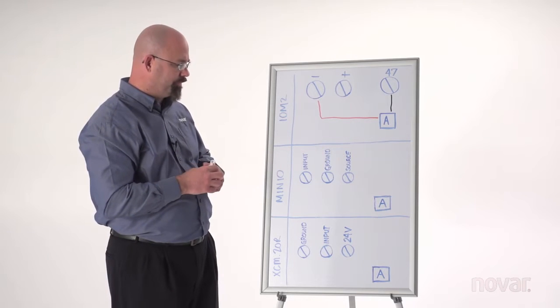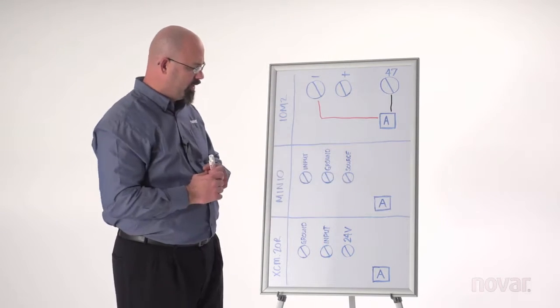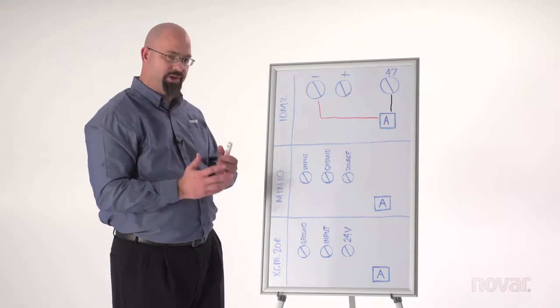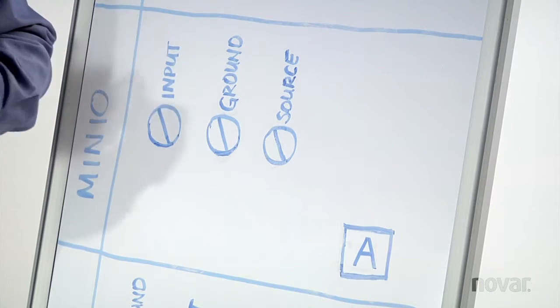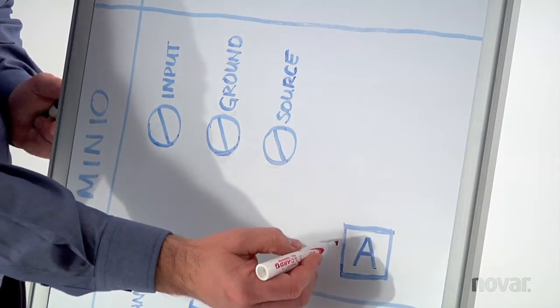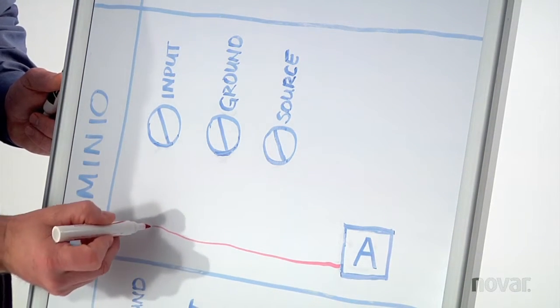We come down here to the MIN-IO. Same scenario, this sensor is remotely powered. So the first terminal we check off that we do not want to use is the source. The source terminal is a 24 volt DC power source. Obviously we don't want that. That sensor has its own transformer. So we'll use the NOVAR white wire again from that sensor's output terminal, and that's going to go to your input terminal here.